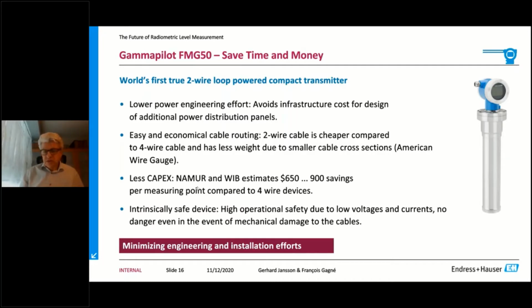NAMUR is something you probably recognize -- this is an organization among chemical companies in Germany, at least where it started. WIB is a user organization in Holland that does evaluations of instruments and so on. They estimate cost savings if you can do a loop-powered instrument installation instead of a 4-wire one. So there's a real cost saving, plus usually it's also easier to do the installation.